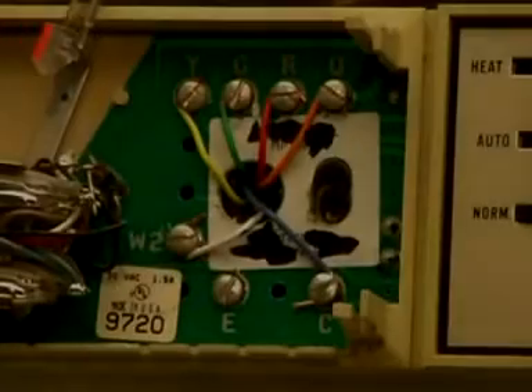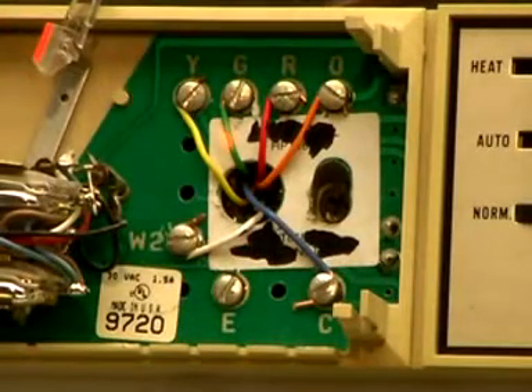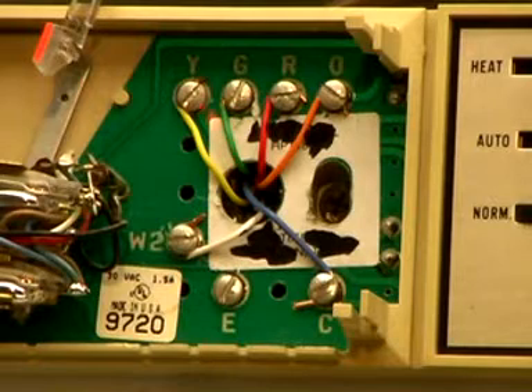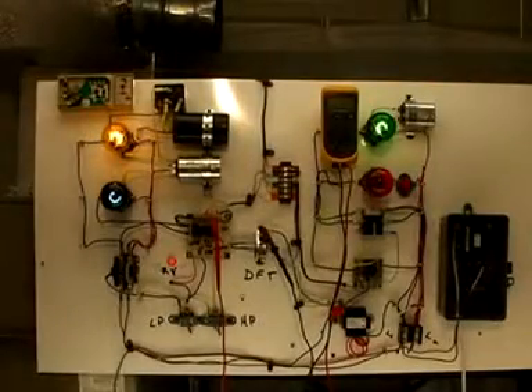Now we can check with this one-piece thermostat, because if the thermostat's telling the Y circuit to energize, then we should be able to read 24 volts on our wire terminal. With the two-piece stat, what you're going to have to do is take the first cover off, actually remove the thermostat wiring, and I'll create some shorts, and we'll see how you might go about eliminating the ones that are not bad and finding the one that is.